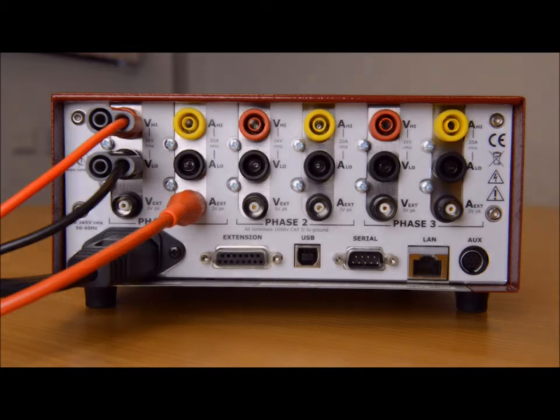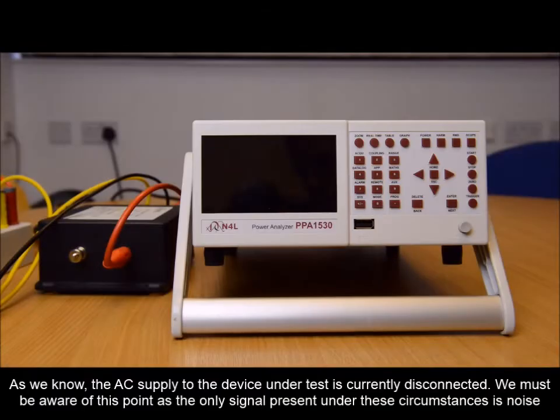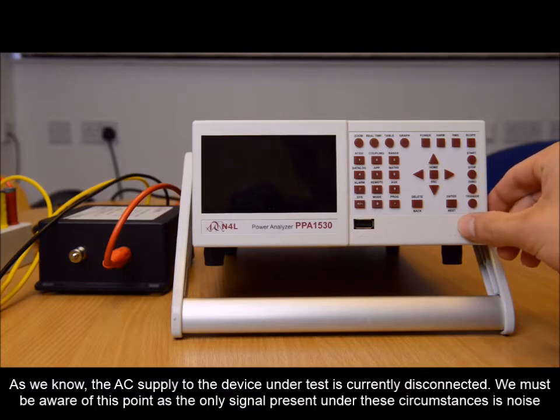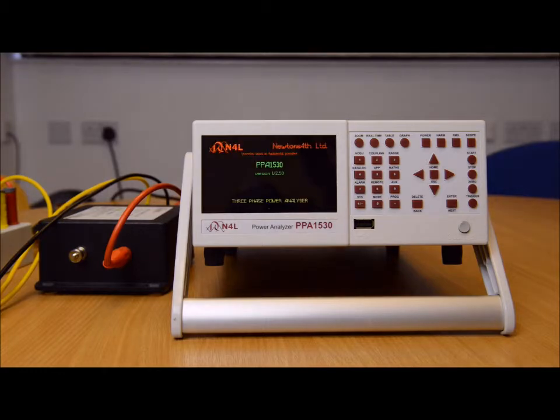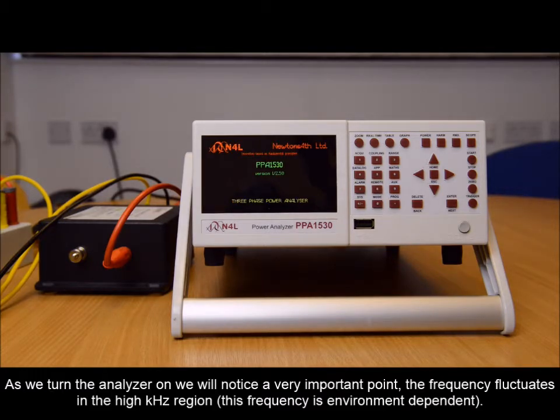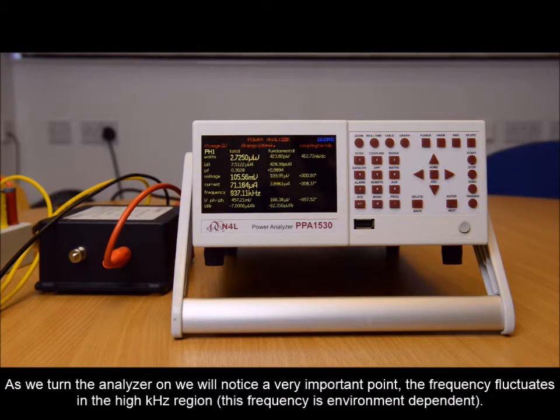Notice we are not using the internal current shunt. As we know, the AC supply to the device under test is currently disconnected. We must be aware of this point, as the only signal present under these circumstances is noise. As we turn the analyzer on, we will notice a very important point: the frequency fluctuates in the high kilohertz region.